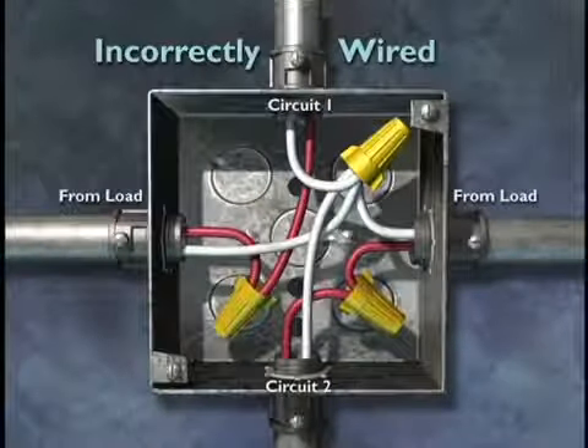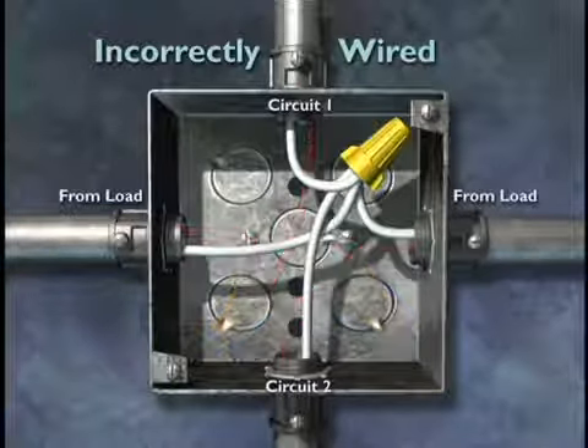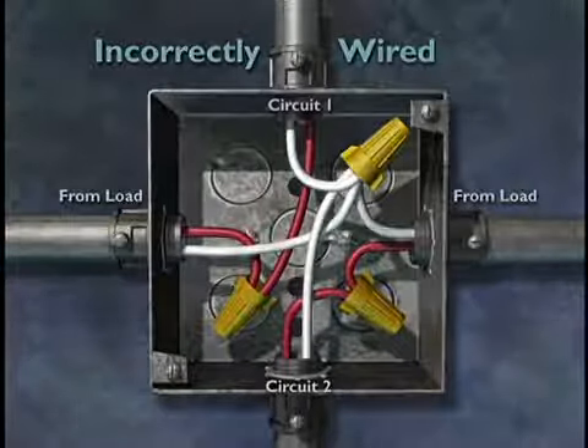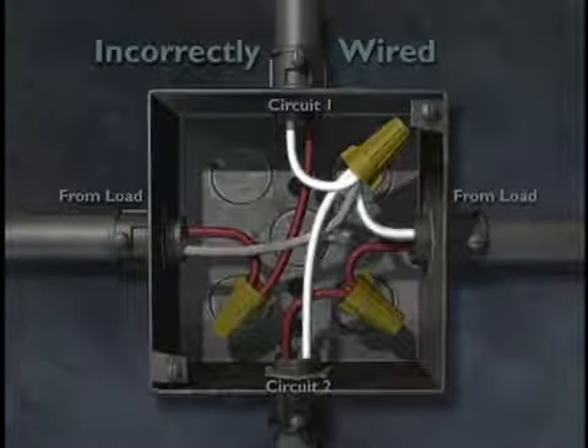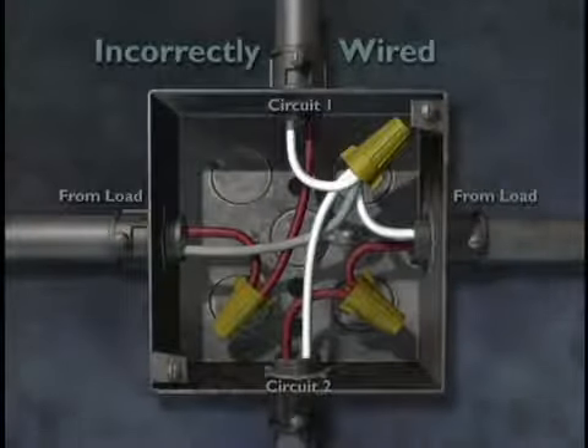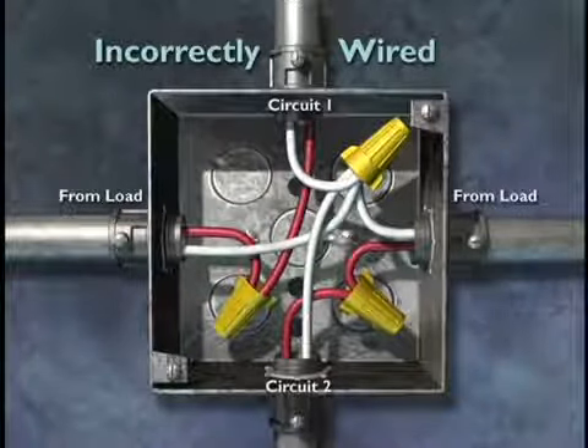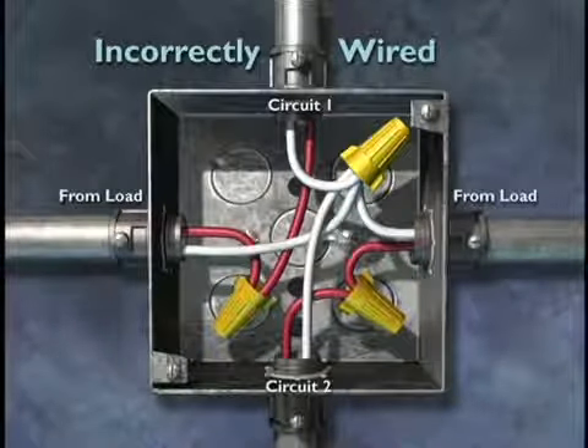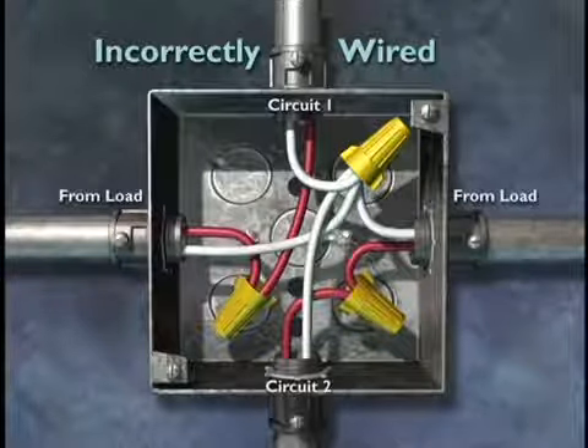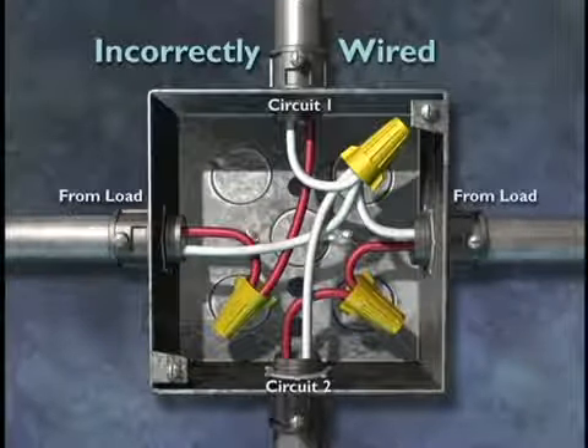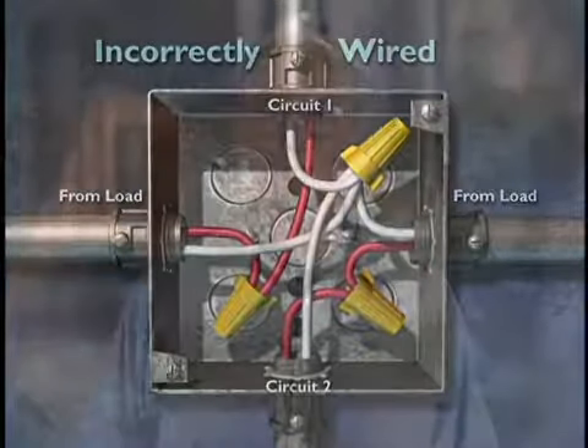Here we see an example of an incorrectly wired junction box in which neutrals from two branch circuits are joined. This wire nut connection allows the neutral from either load to run in both circuits in parallel paths in different cables or conduits. In this situation, when the neutral return current from either load reaches the wire nut, instead of going back with its corresponding hot, it splits and goes back on both circuits. This connection violates both National Electrical Code sections 300-3B and 310-4.